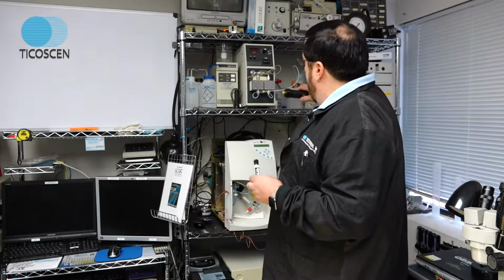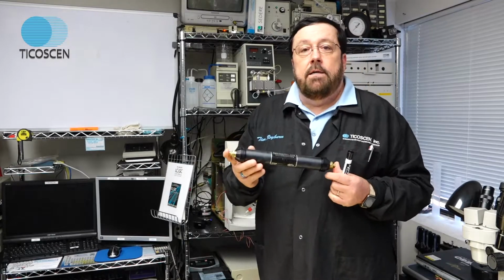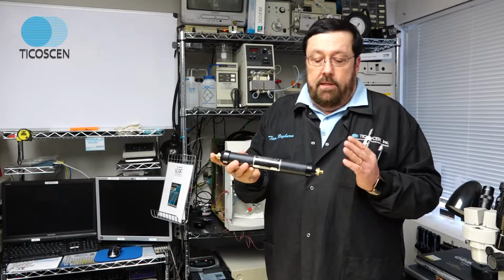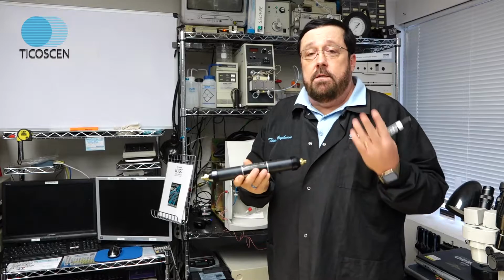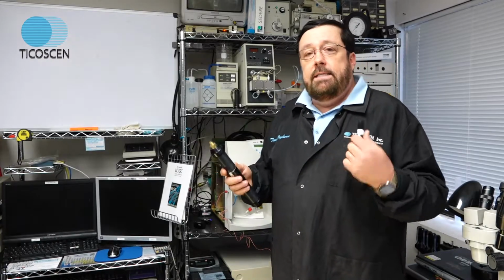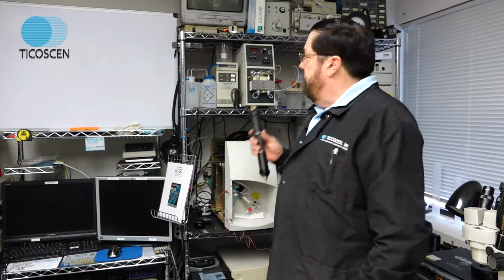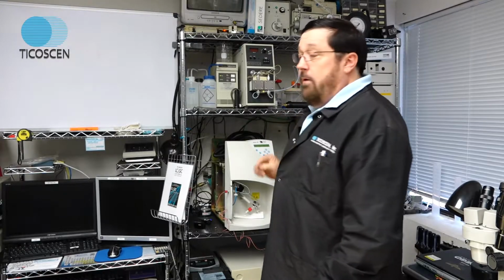you'll need to run a desiccant trap or a hydrocarbon trap like this. You need to put that in line in your dry air to keep the contaminants from getting into the detector, because the detector will see those things. Ideally, you should use nitrogen, pure nitrogen.